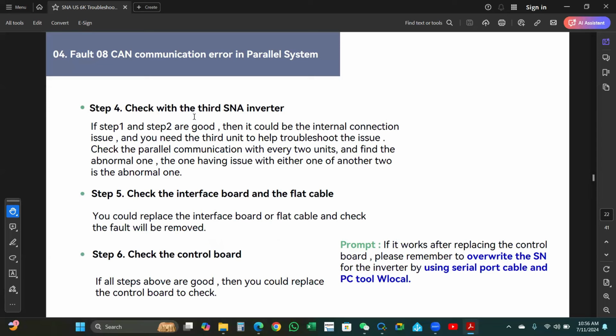Step 4, check with a third SNA inverter. If steps 1 and 2 are good, then it could be an internal connection issue, and you will need a third unit to help troubleshoot the issue. Check the parallel communication with every 2 units and find the abnormal one. The one having an issue with either one or the other in the 2-by-2 tests is the abnormal one.